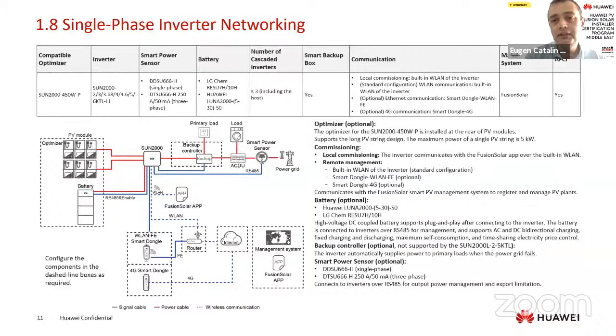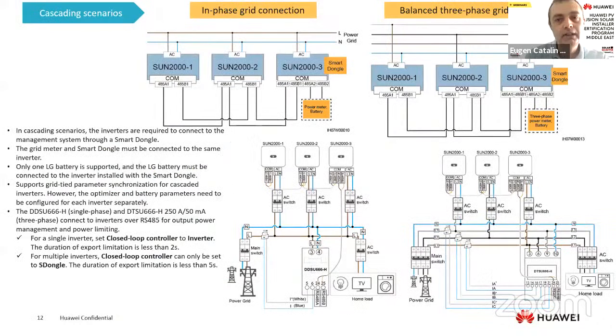To commission the inverter, of course, we will use Fusion Solar, as you already know, to connect to the inverter and perform the quick settings. We will see later the steps of the quick settings and what we need to do to set the inverter. In the cascading scenario with L1, the single phase, as you can see here, a maximum of 3 inverters can be installed in a single phase grid or a 3-phase grid, as in this schematic.